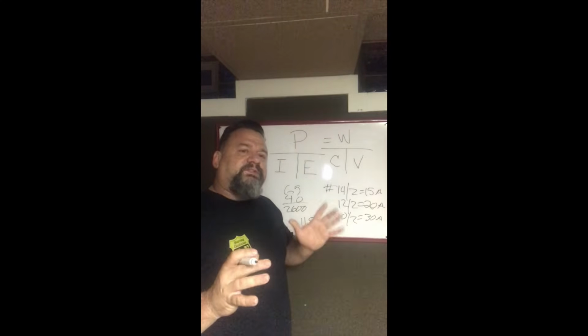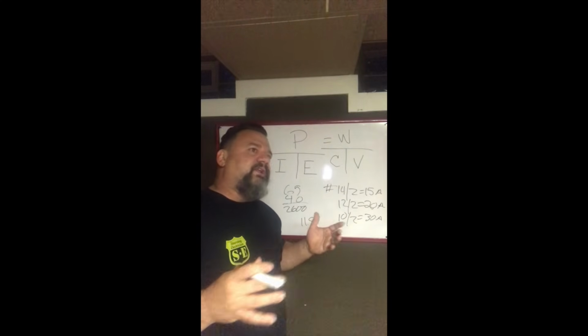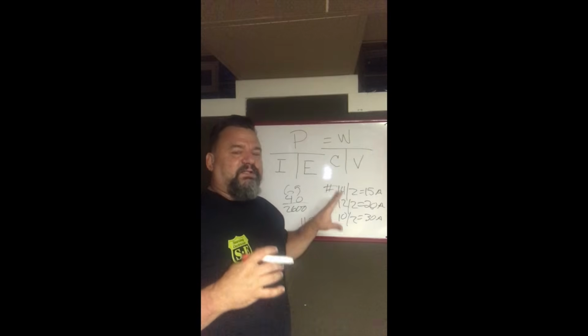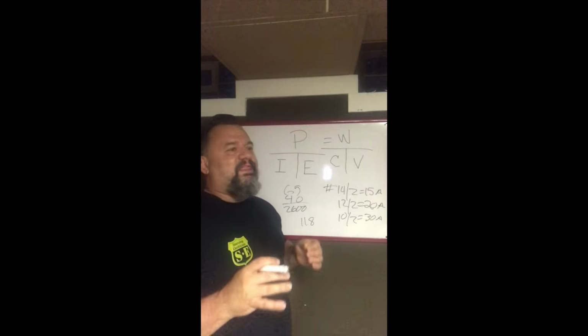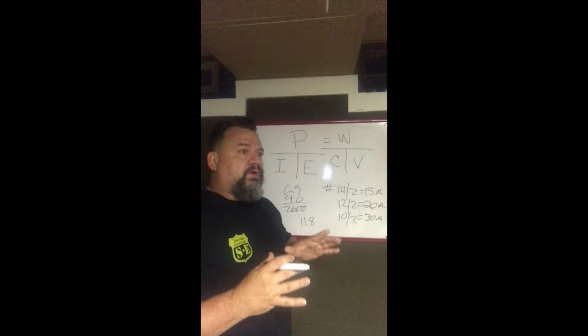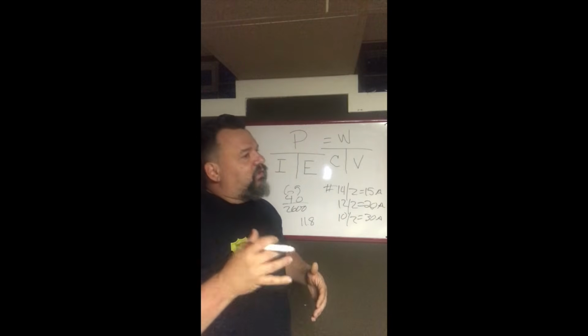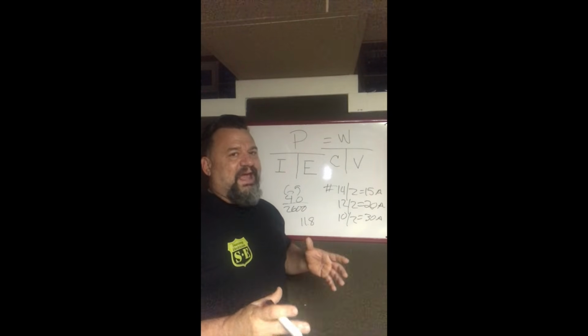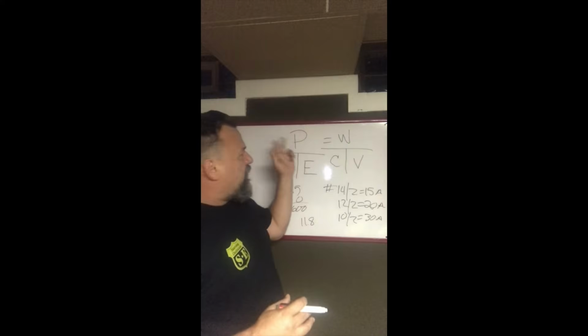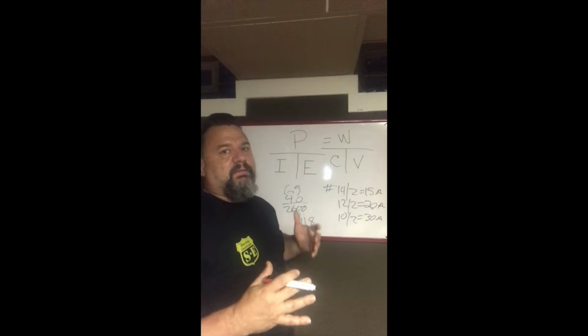And the code says, it's not that new, but any of the plugs in the bathroom have to be on a 20 amp circuit, by themselves. So they're not drawing off of anything else. Blow dryers, curling irons, stuff like that will draw more power from that circuit, and then it'll max you out quicker.